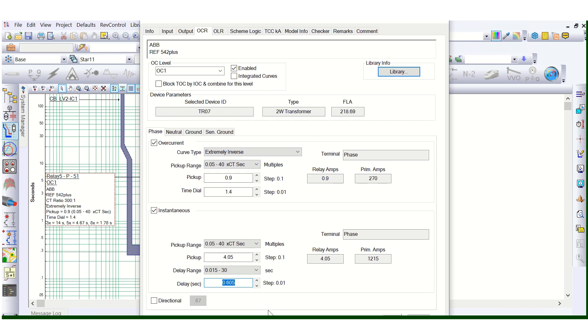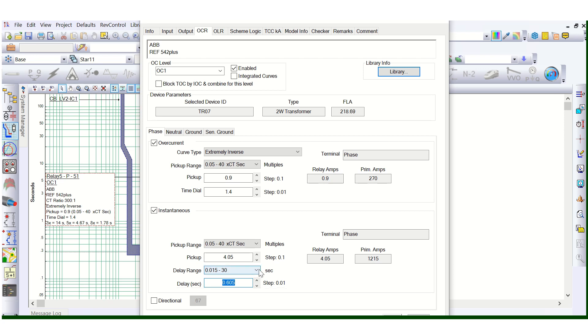Basically this is not actually instantaneous — this is short time delay. It will be called instantaneous when there is no time delay. Ideally speaking, this delay time cannot be exactly 0 seconds, but there should be no intentional time delay — that's the definition of the instantaneous setting. The minimum delay range here is 0.015 seconds.